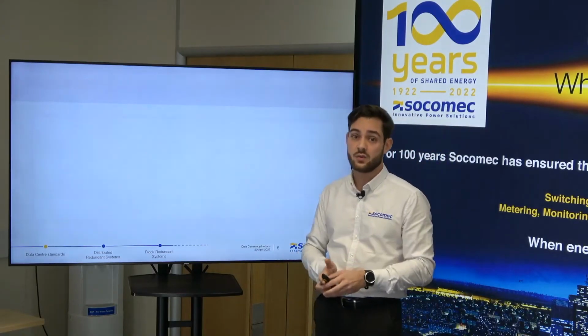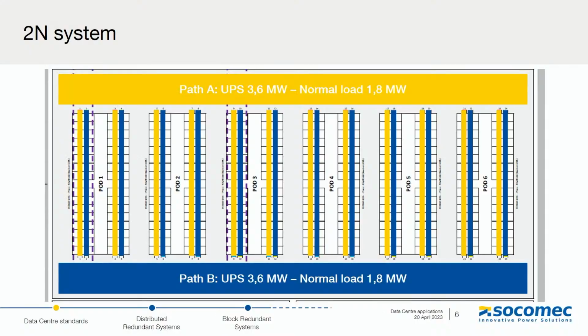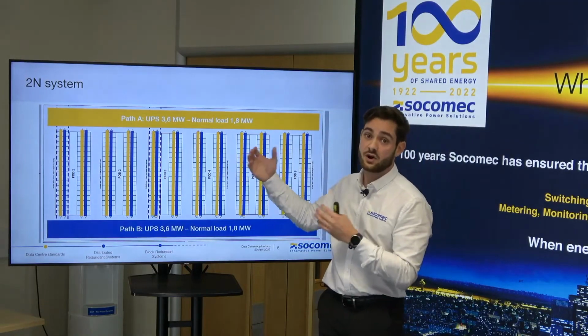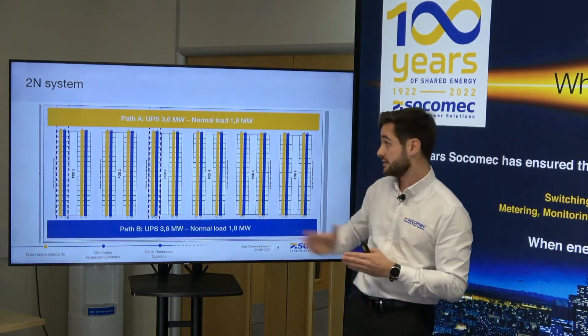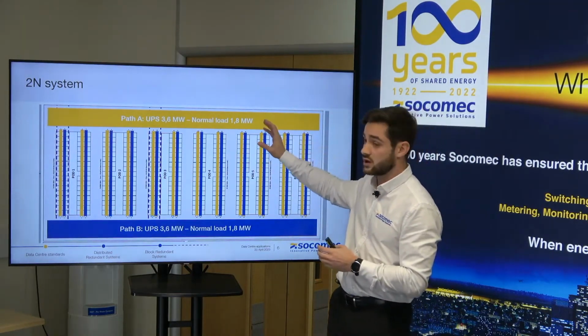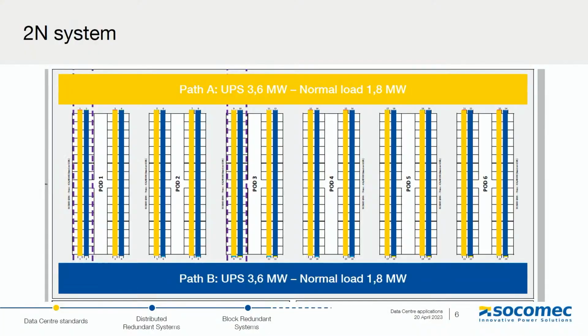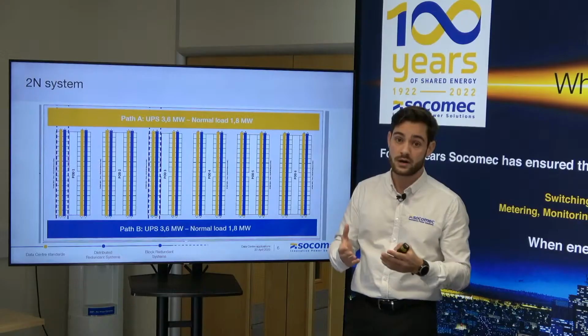If we have a look now within the data hall, exactly the same. So we have a load of 3.6 megawatts. In normal condition, as we said, we are dual corded. We have a dual power supply on the dual corded servers. So we would run at 50% on each leg, as Richard just explained. So basically 1.8 megawatt on one path and the same on the other one. It means that the UPS system would work at 50% to cover the load in normal condition.